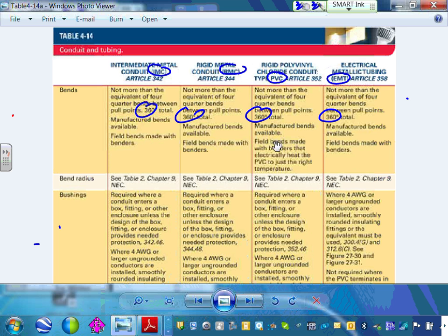You cannot bend more. You guys, do you know how bending conduit works? You bend it 90 or 75, you keep adding the bends. So if you have a conduit, you go this way, this way, this way. Here's 90, 90, 90, and I started right here, so I can go one more 90 here. Does that work? 1, 2, 3, 4. 4 90s, so I'm going back to where I started. But now what happens if you need 5 90s or another bend? It doesn't have to be 90, it could be 80.